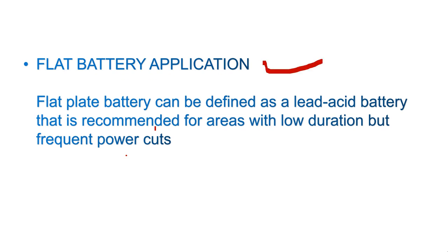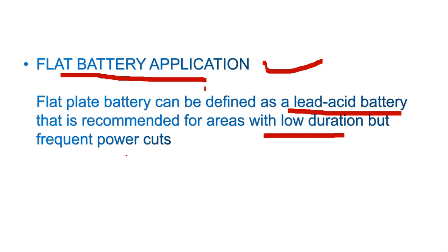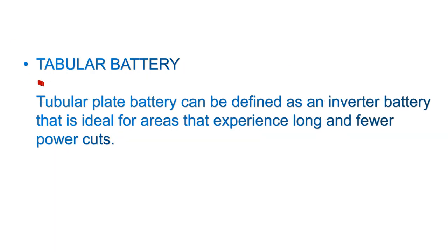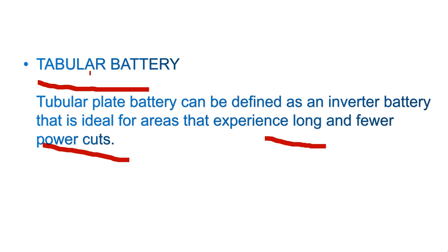The flat plate battery is a lead acid battery used where there are frequent but short power cuts — like 10 minutes, 20 minutes, or up to half an hour to one hour. If you need more than two to three hours of backup, you must go for a tubular battery. Tubular batteries are designed for longer power cuts and have much greater capacity to withstand longer backup times.